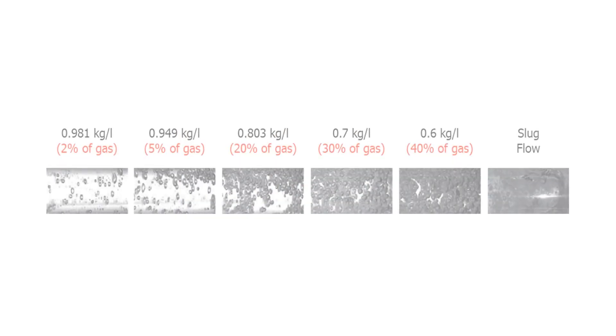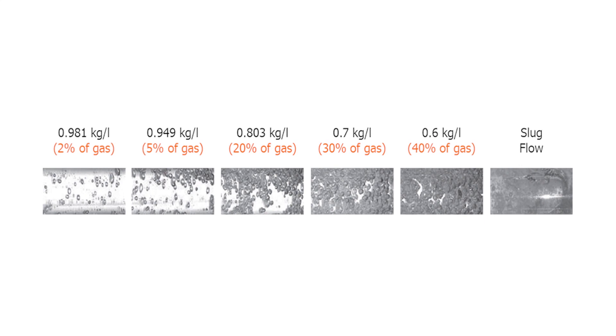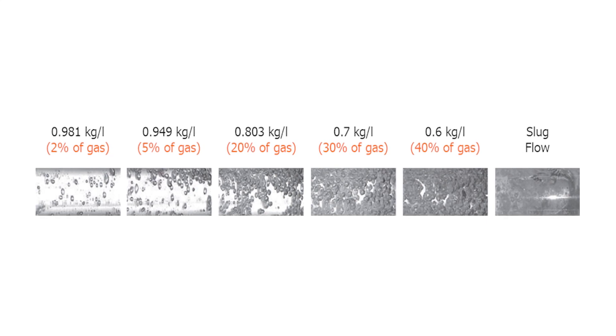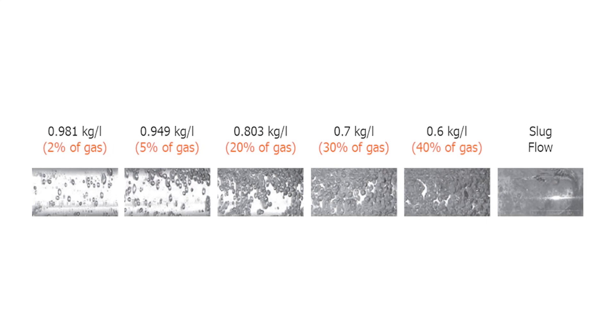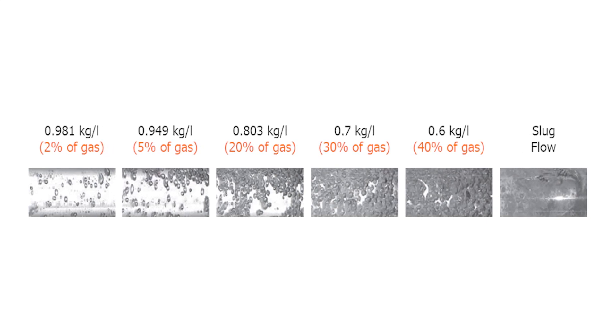The entrained gas in the oil-water emulsion could range from 2% to as high as 40%. This entrained gas, or GVF, in the oil-water emulsion will cause two major impacts on the Coriolis flow meter's performance.